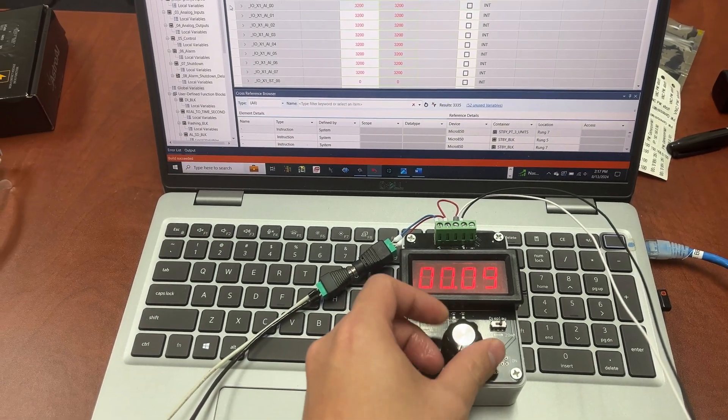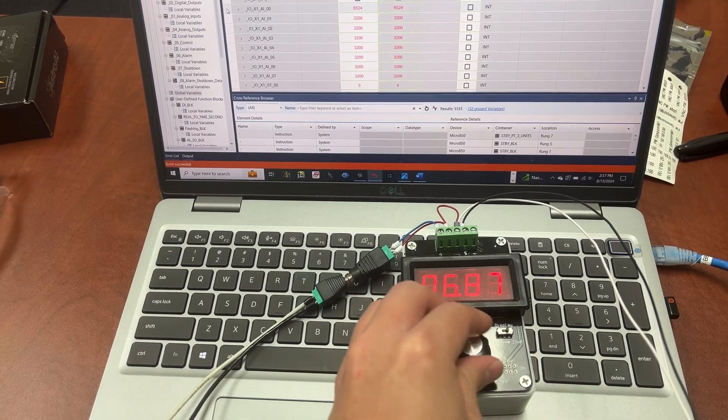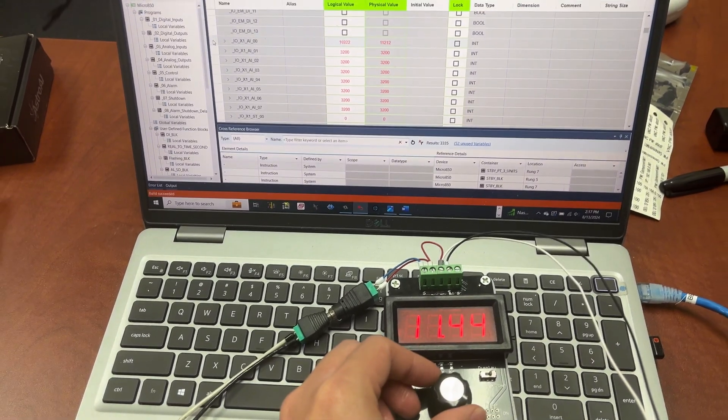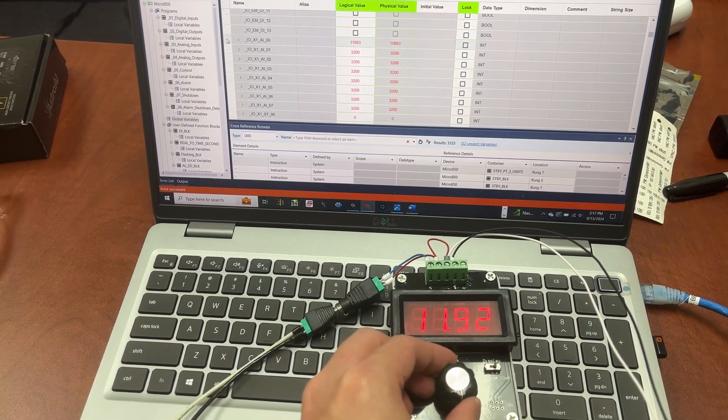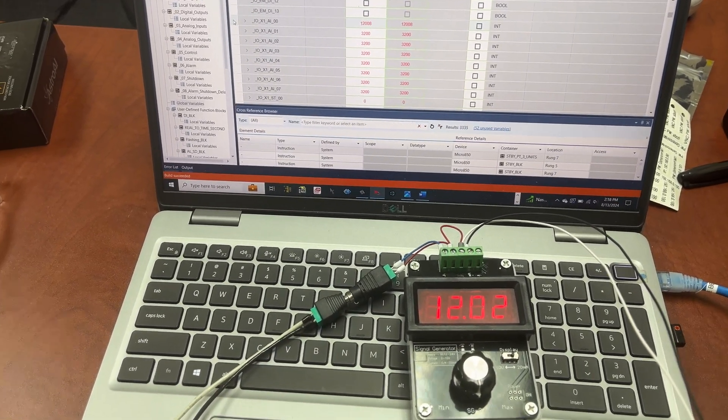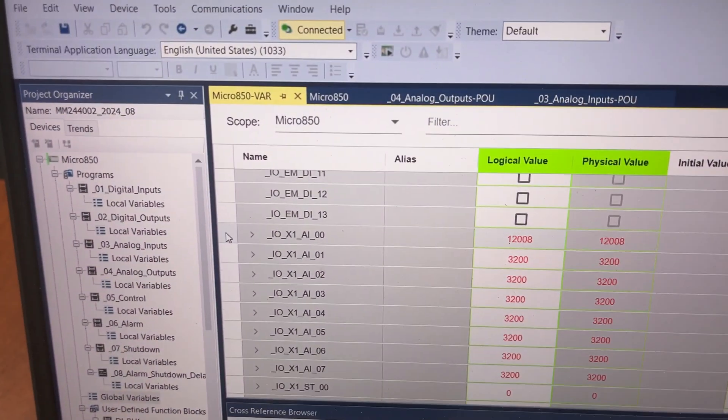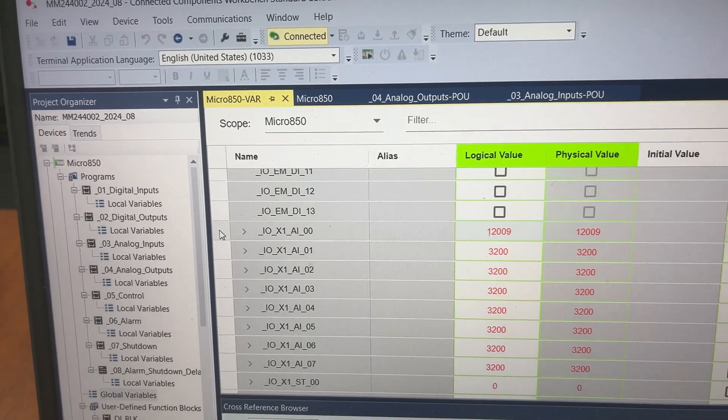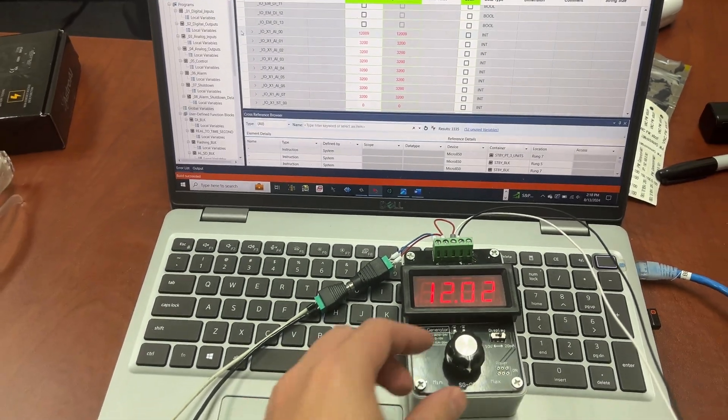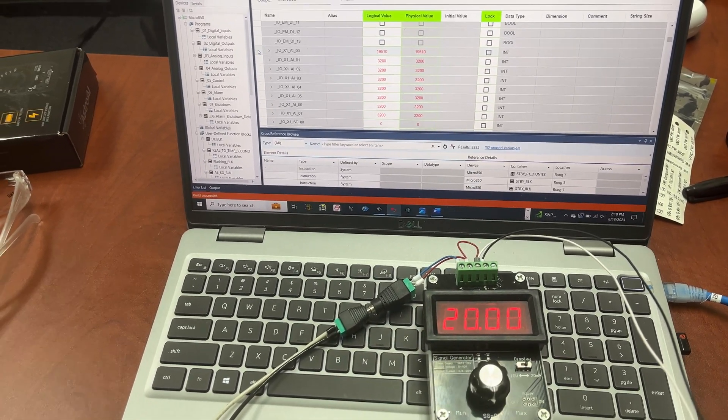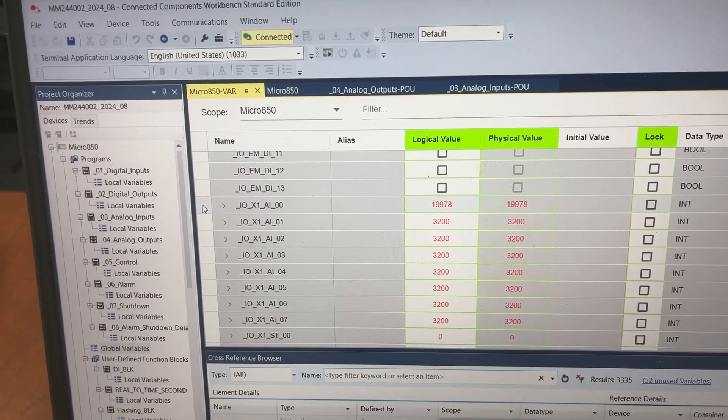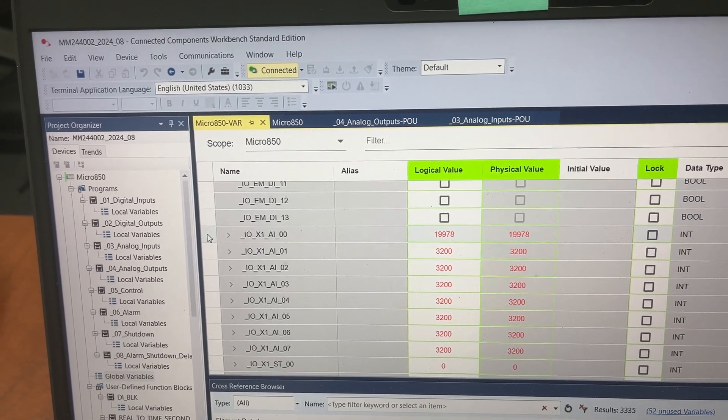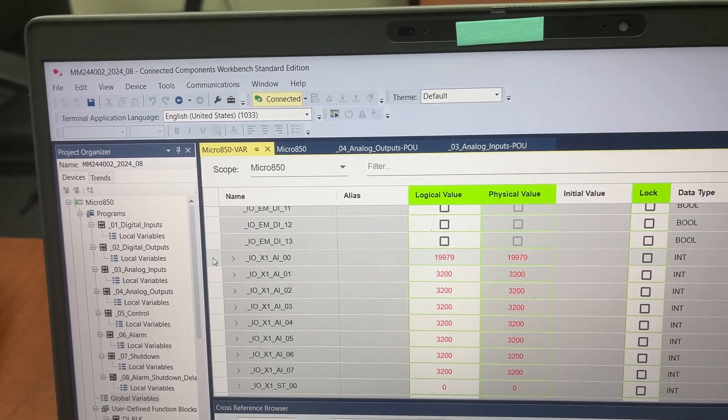Now let's increase the milliamp signal to 12 milliamp. At 12 milliamp, the PLC tag value is 12,008. Now let's increase it all the way up to 20 milliamp. At 20 milliamp, the PLC tag value is almost 20,000. It actually is 19,978-79.